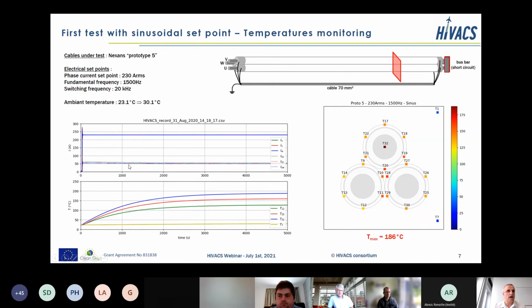What is interesting also, in the dashed plot you see the induced current in the EMC braid, in the shield, and it's also quite constant and well balanced between the three shields. When we wait for a steady state temperature, we can see on the plot on the right a cut in which we represent all the sensors used, with one sensor in the middle of a conductor and another on the surface. The color of the square is linked to the temperature, and you see the color bar on the right. As expected, the maximum temperature is in the middle of the top conductor, and the lowest temperature, except for ambient, is on the surface at the bottom.